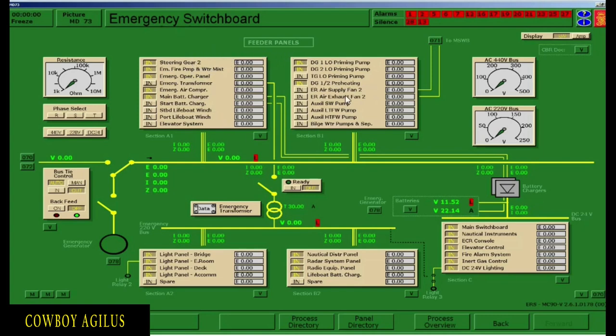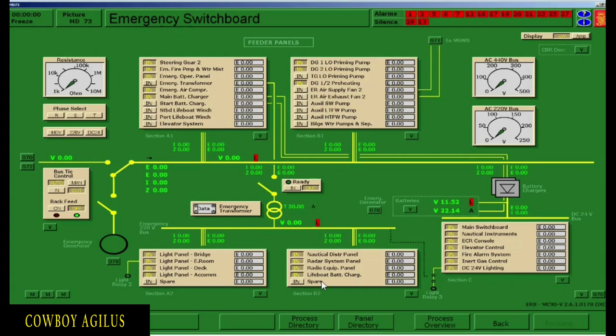These consumers above are 440 volts, while these ones below are 220 volts. So in order to have a 220 volts supply, connect this breaker for the emergency transformer by clicking in. Then check that these breakers are pushed in. This group are 24 volts — they are supplied by batteries, so put everything in as well. In short, click in all the breakers except for spare. Do not include the spare — spare means nothing is connected to that breaker.